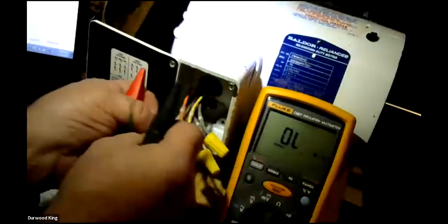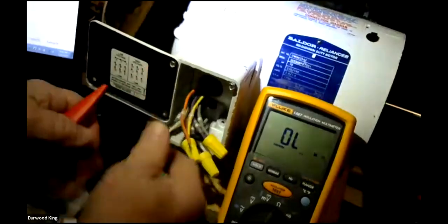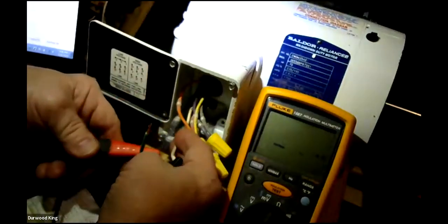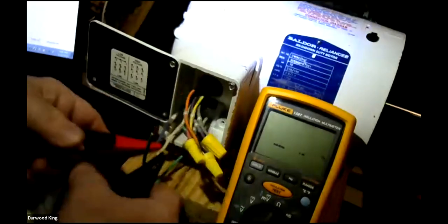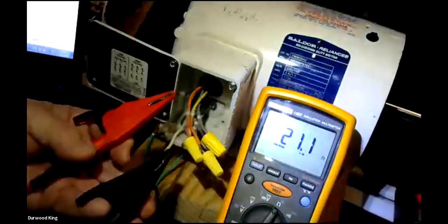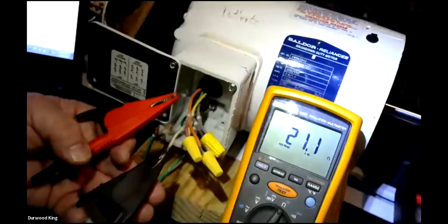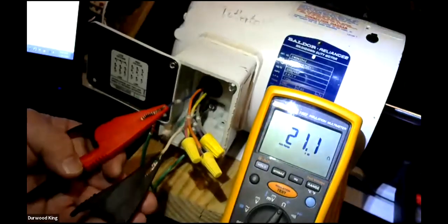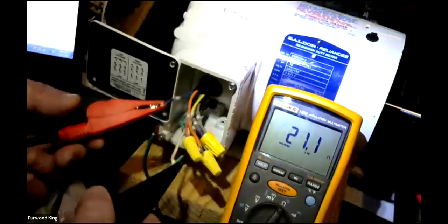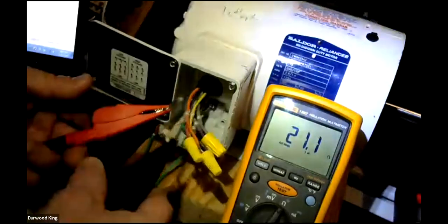So now we're going to go from 1 to 2. So 1 to 2 is reading what? 21. Well, how do we know if maybe we have a bad motor? How do we know we're supposed to get that number? Is there something on that motor tag? No, it doesn't tell you what it's supposed to be. You'd have to compare it to another motor that's like it. They don't tell you what the ohms would be. I've never seen that included on a motor anywhere. But if you got another one like that in the plant, then you need to quickly check one that actually works right.